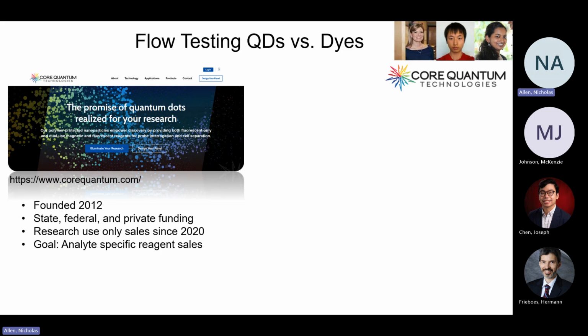There's a third category called analyte-specific reagents, though. This is the easiest possible path to FDA approval. And what it is, is the reagent used in the test. And all you have to do is show that it works the same or better than the reagent currently used. You register with the FDA, you have to have ISO certification, but there's no approval per se in the classical sense. The downside is every lab that uses your product has to validate it at their site individually. That's kind of how the ASR system works. But that is what we chose to go after because that made the most sense for our product.